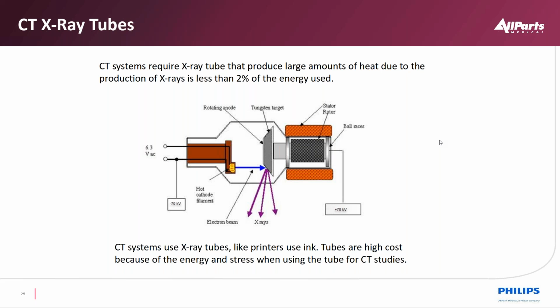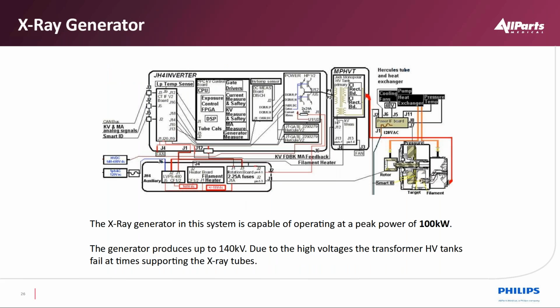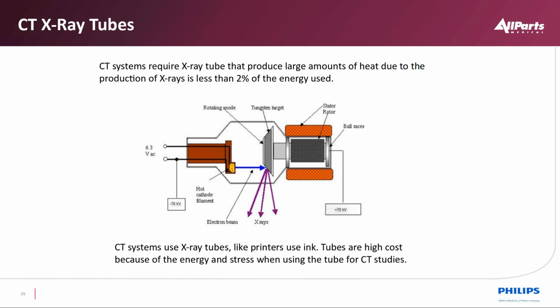Most CTs up to 64 slice, 128 use a 7-degree target. And then we get into the 256s and higher, and that uses a different 11-degree target. I'll go back just a second. One of the things that we do on the tubes, basically they are our printer cartridge for CT.